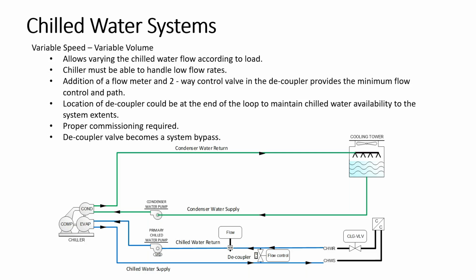We actually have a flow meter in this system. And if the coils out there need water, they open up or close their two-way valves as needed. So we both control the amount of water we send out to the cooling coils, but we also maintain a minimum flow on the chiller to keep it online. And if it has a very low turn down where it can go very low in its capacity, we can unload the chiller, we can unload the flow of the water. We're actually saving energy now, to where we can match the flow necessary for the system to the flow necessary to keep the chiller running at its most efficient point.